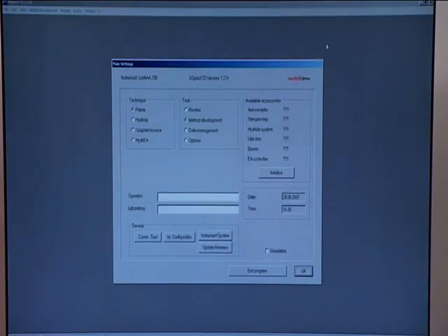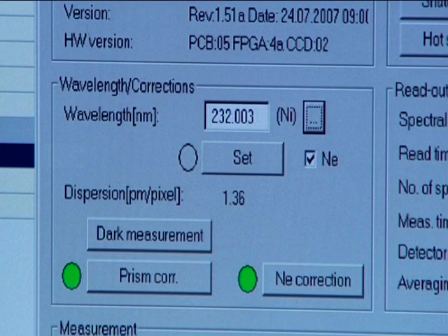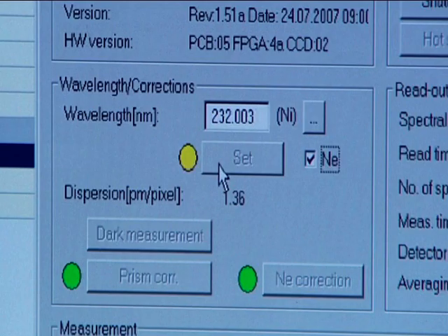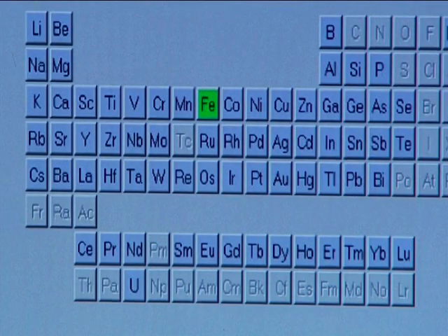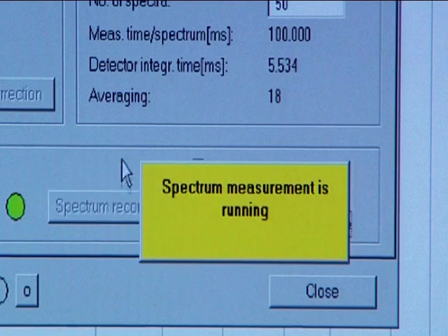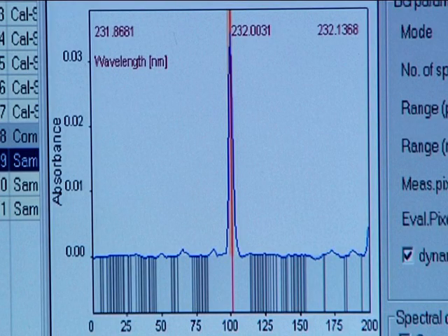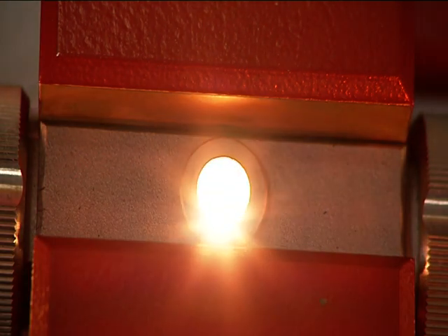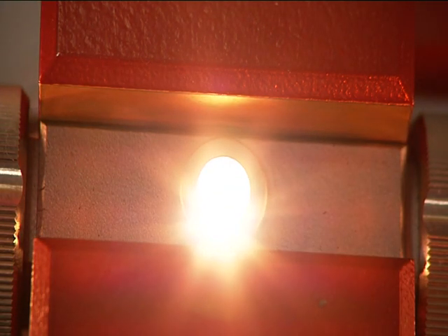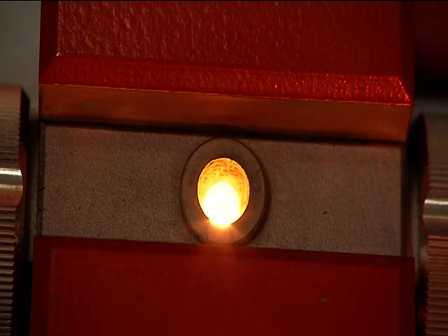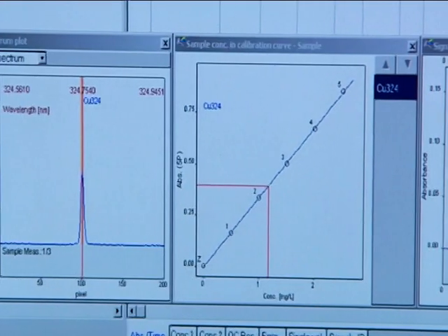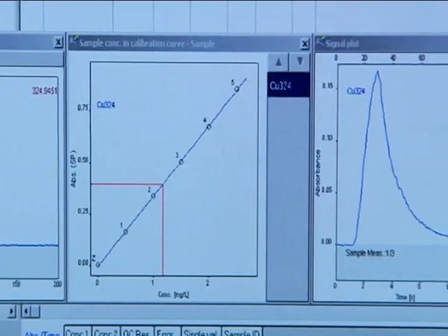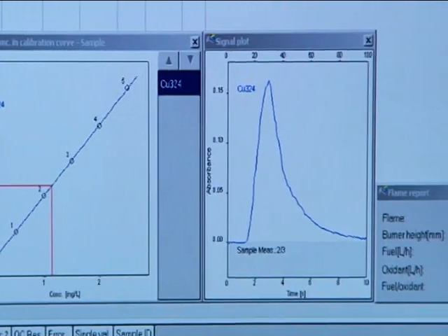Previously, single-element methods predominated. With this technique, multi-element determinations become standard. For the first time, complete spectra are measured by AAS. This opens up completely new optimizing and correction possibilities for their use.